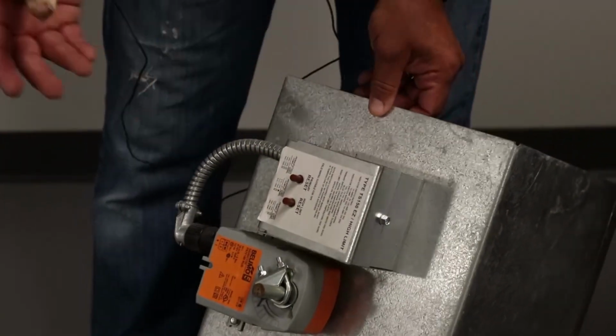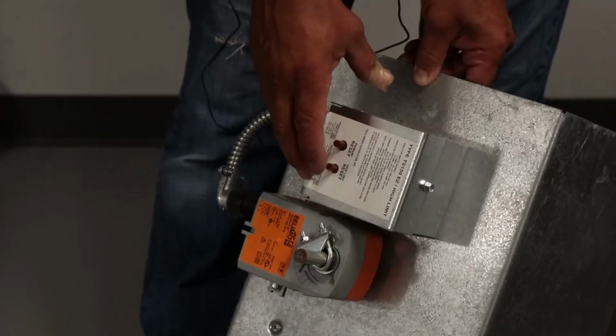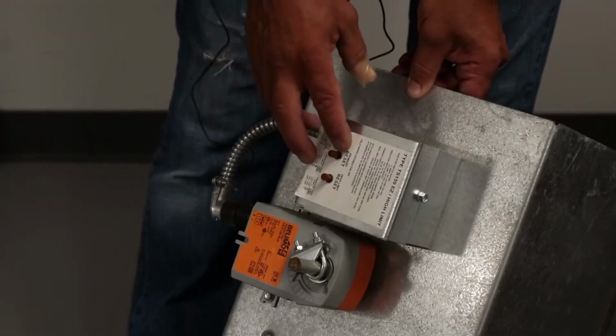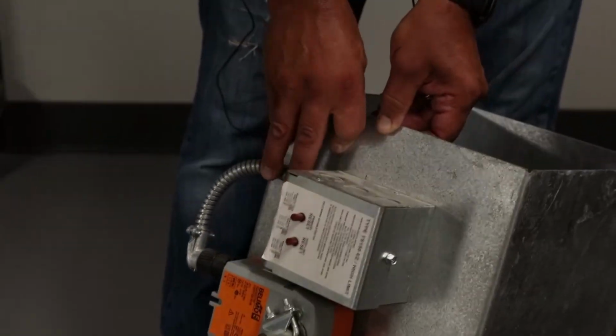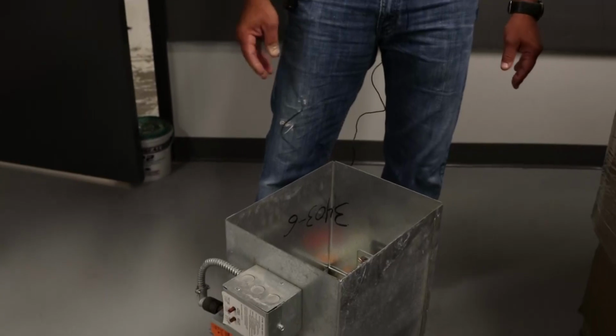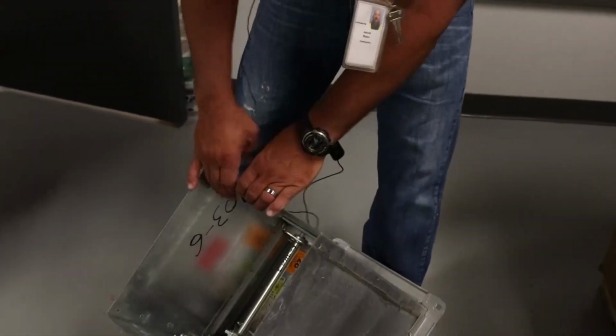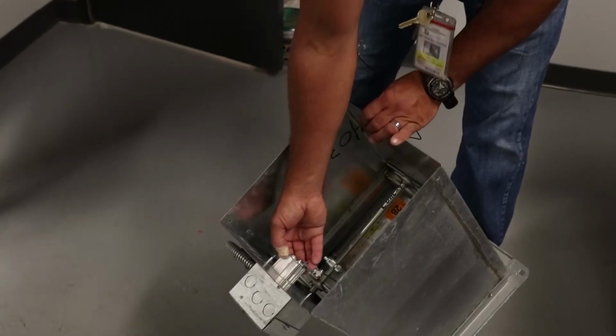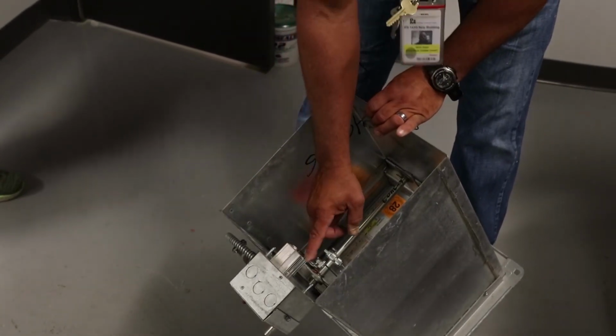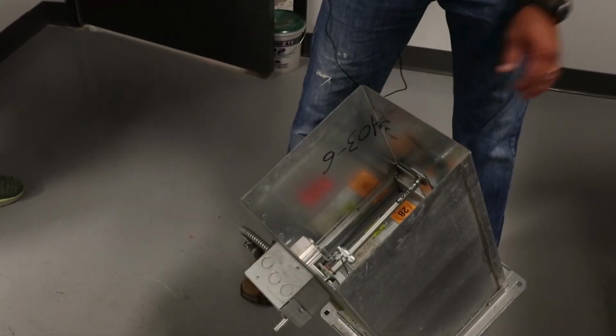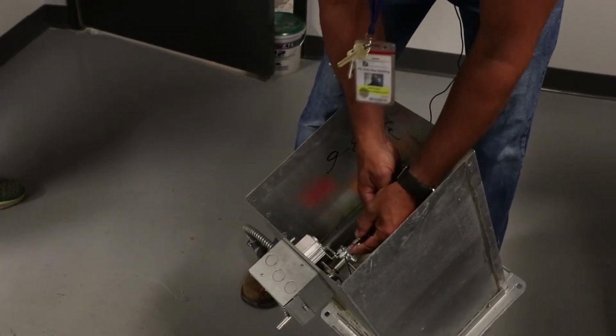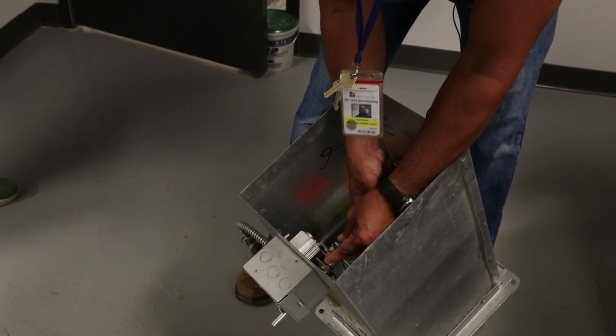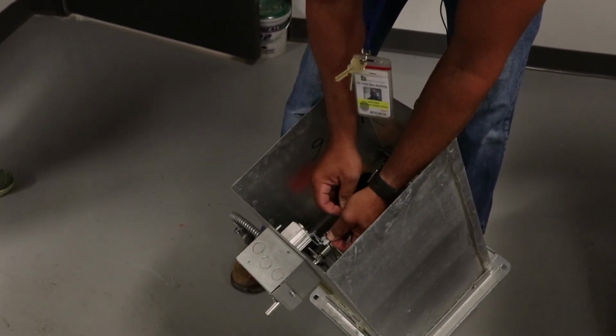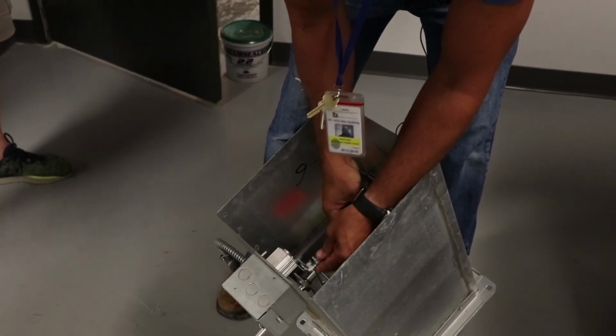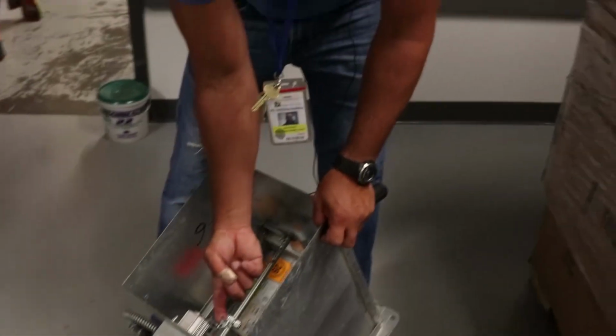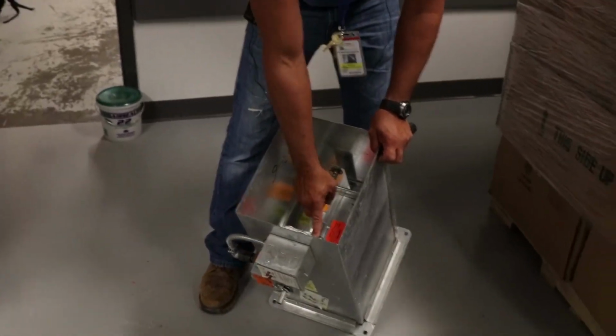Right, so if you ever get a damper that's not open and has power, it could be that one of these temperature sensors went bad or tripped. You can reset these first. It's just in series with the power wiring. There is on this one here, if you look inside, a position indicator which reports back to your fire alarm system. So if I was to loosen this thing up, based on where the damper is, it shows that it's being opened or closed.